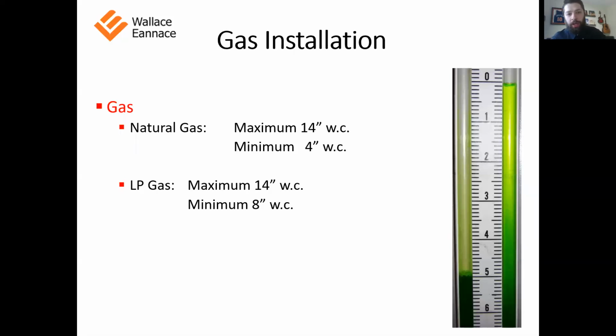Gas installation, the Crest units can take between 4 and 14-inch water column. Functional range, I know some of our competitors, you have to have 14-inch water column. We don't. 4 to 14 is fine. You just want to make sure you're not having any drastic drops in pressure when you start your unit.